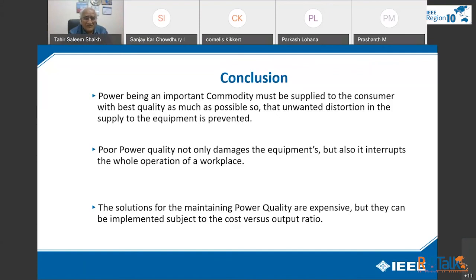The solutions for meeting power quality are expensive, but they can be applied subject to cost. You have to see for yourself. But in our country, I have seen the industrial sector is most negligent on this issue. So they have a lot of problems with harmonic distortion. Sometimes the motor burns, the transmission line burns, and the AVR of a generator burns, even a standby generator. So you have to be very careful in giving power to your equipment.